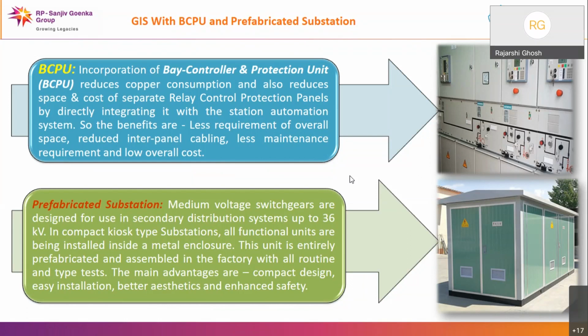We also have prefabricated substations at the medium voltage level, which we can install in housing complexes, some industries or some shopping malls. All functional units are installed inside a metal enclosure, and the unit is entirely prefabricated and assembled in the factory with all routine and type tests conducted there. The main advantages are compact design, easy installation, better aesthetics, and enhanced safety both for the operators as well as for the customers. The main thing is they're very easy to install, and without any difficulty, you can commission the substation within a very short time.